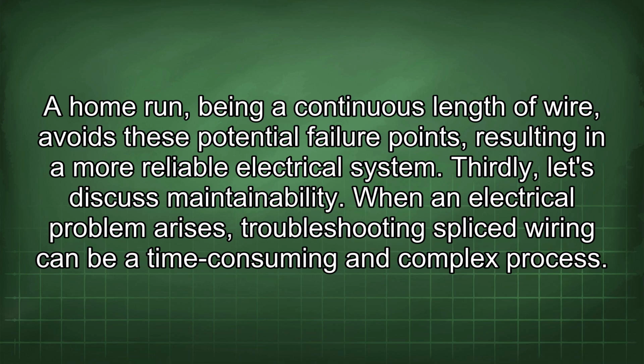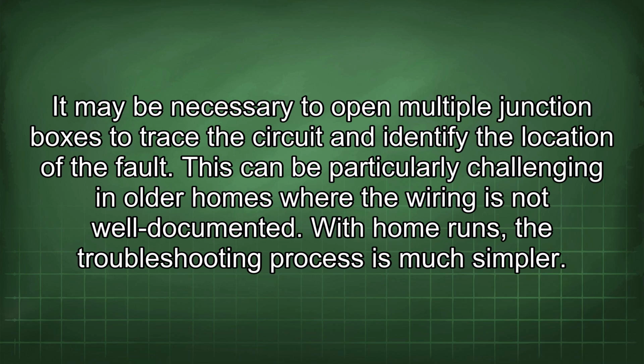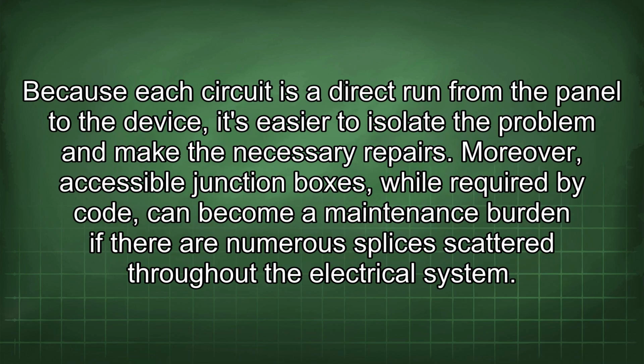When an electrical problem arises, troubleshooting spliced wiring can be a time-consuming and complex process. It may be necessary to open multiple junction boxes to trace the circuit and identify the location of the fault. This can be particularly challenging in older homes where the wiring is not well documented. With home runs, the troubleshooting process is much simpler. Because each circuit is a direct run from the panel to the device, it's easier to isolate the problem and make the necessary repairs.